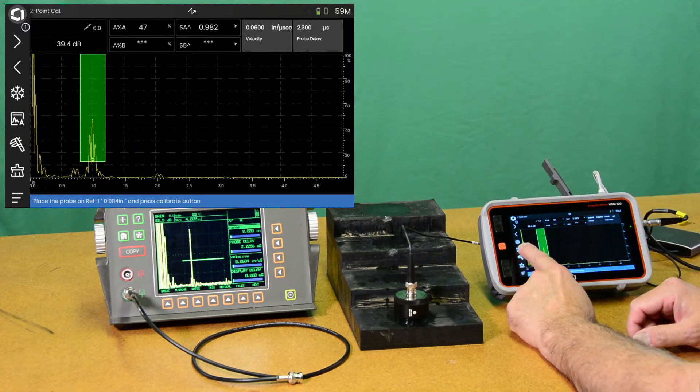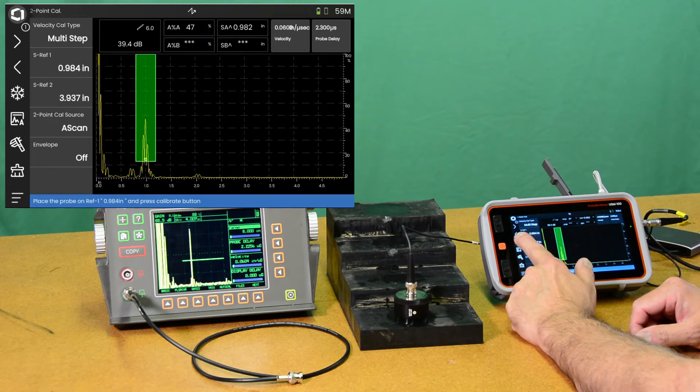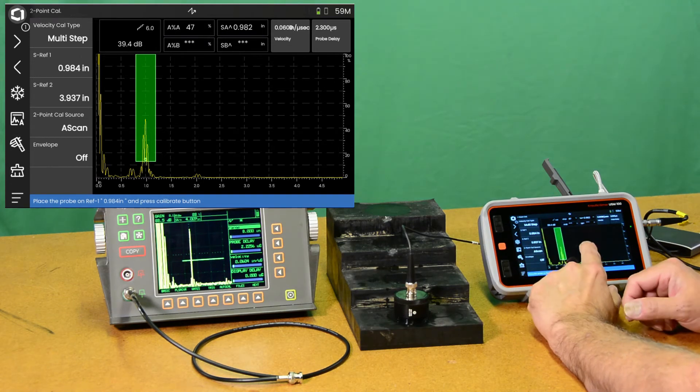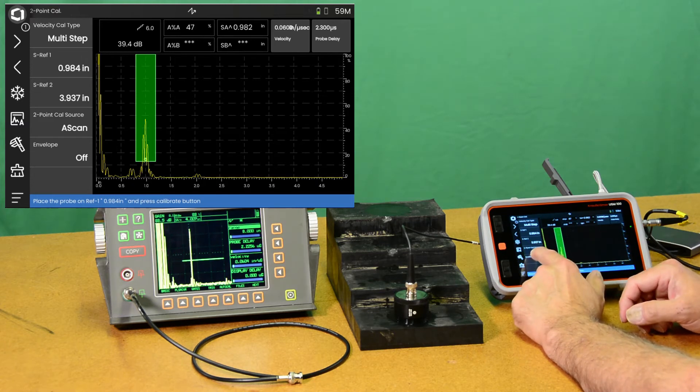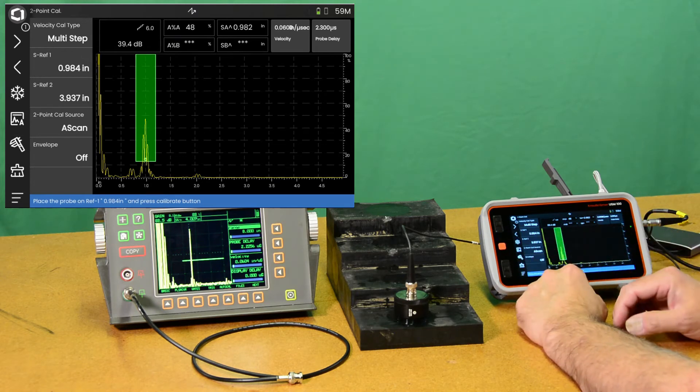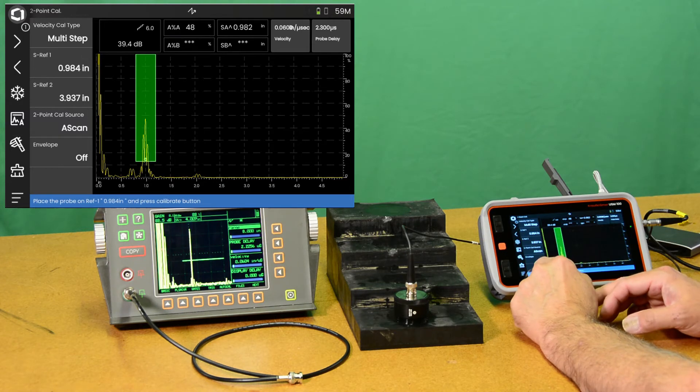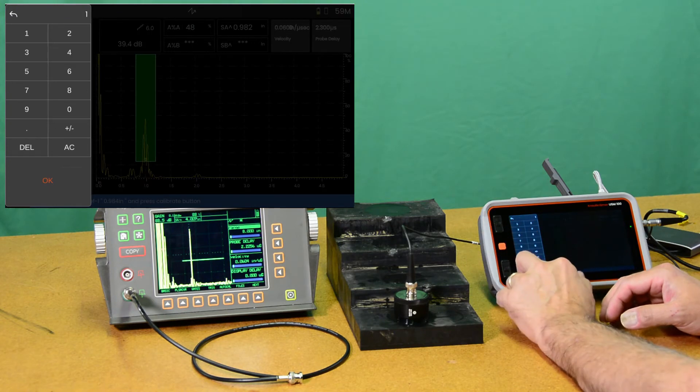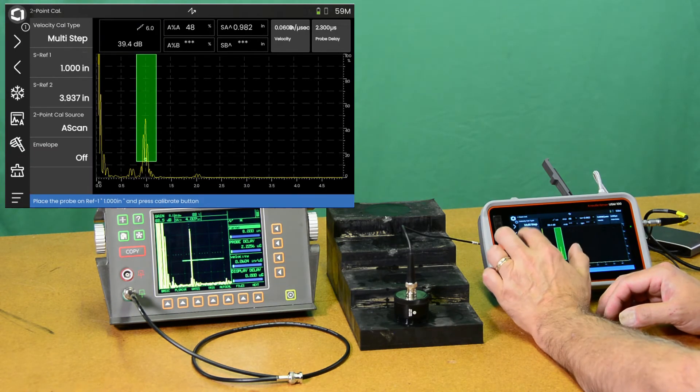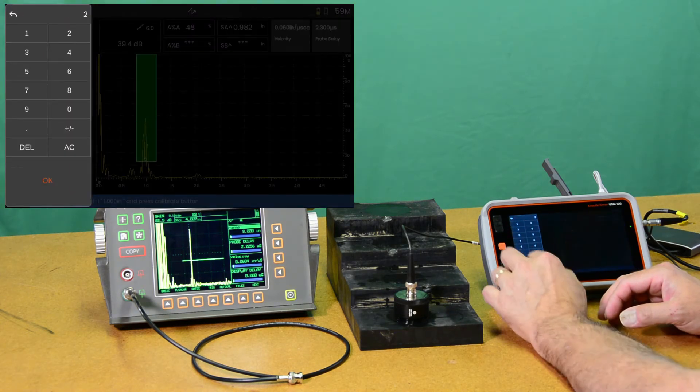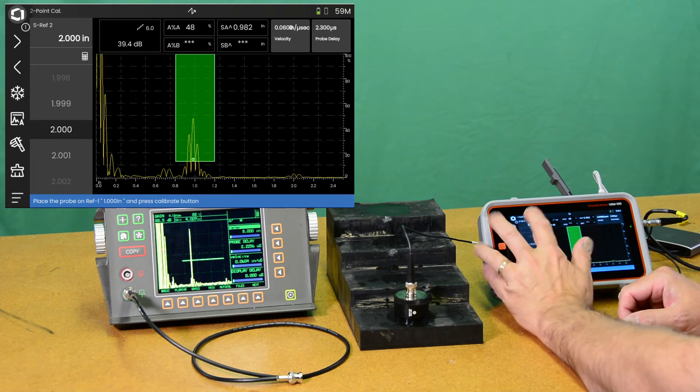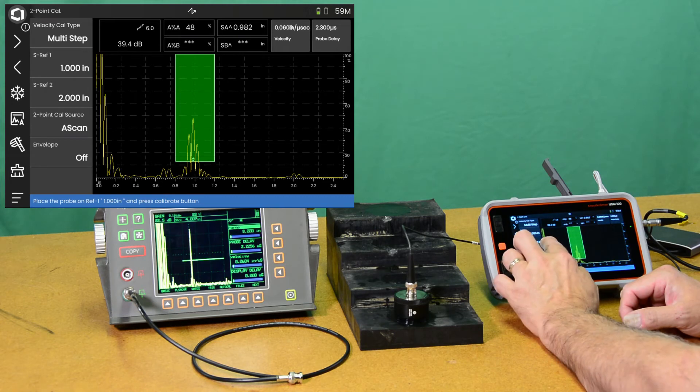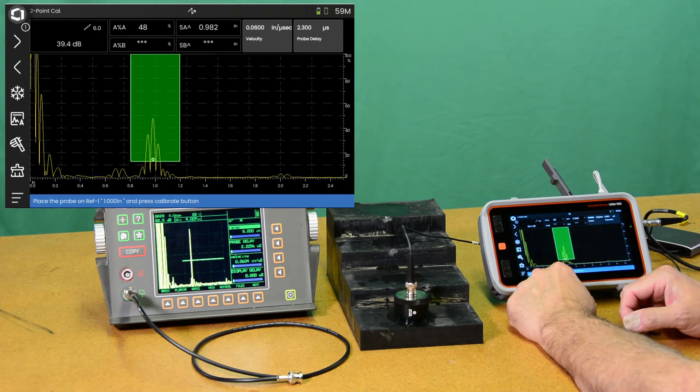So now we can swipe out the sidebar. This is a special feature of the USM 100. The sidebar menu is a special menu that's present on each of the panels. And it has some of the most commonly used controls for that panel right at your fingertips. So this is our two point calibration panel for velocity and probe delay. The two most frequently used controls are going to be our reference one thickness and the thickness of the second. So we're going to tell it we want to look at one inch and two inch.